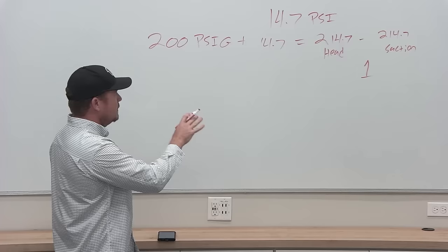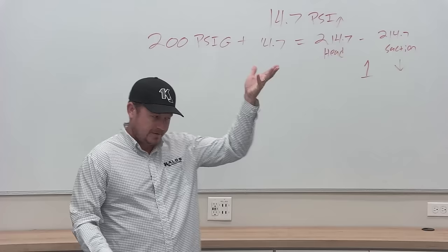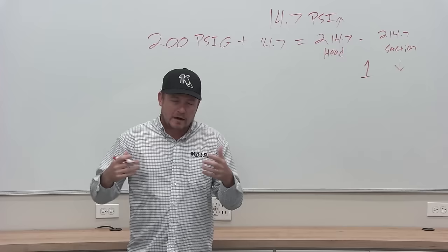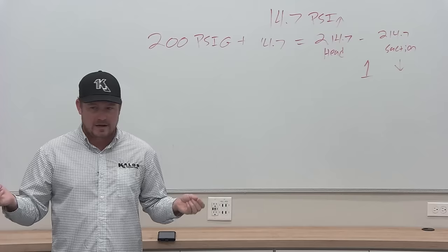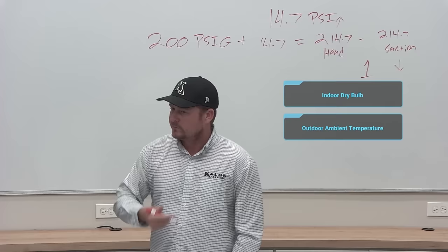When the system comes on, the head pressure goes up and the suction pressure goes down — that's what the compressor does; it creates a differential. You're rarely going to actually calculate compression ratio; you're going to look at other numbers to tell you what your head and suction should be. You look at your indoor return temperature and your outdoor ambient temperature — those are the two primary drivers of head pressure and suction pressure.